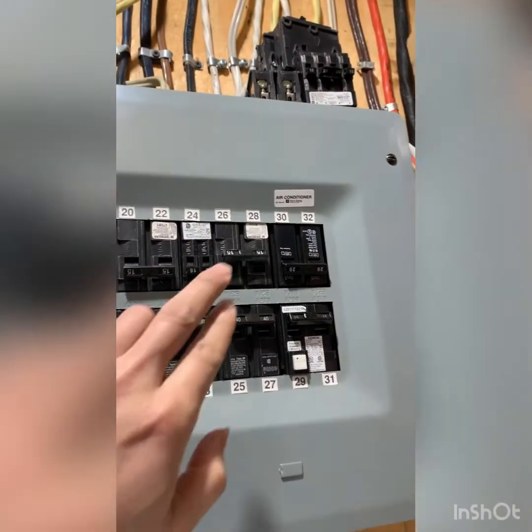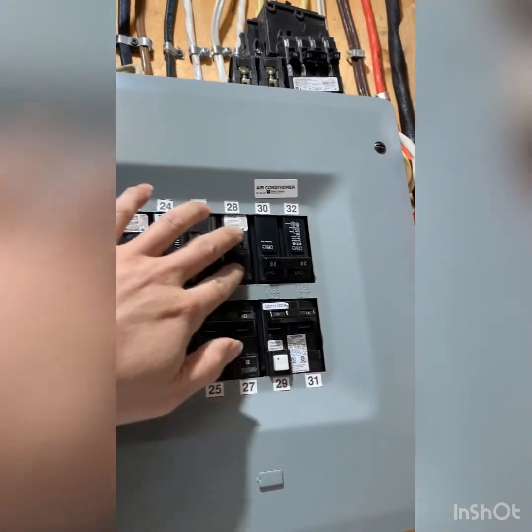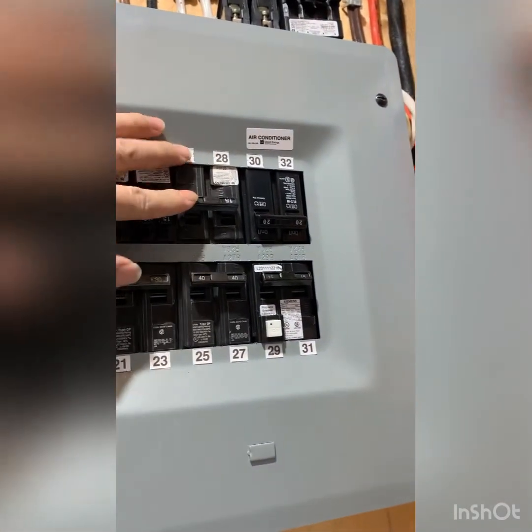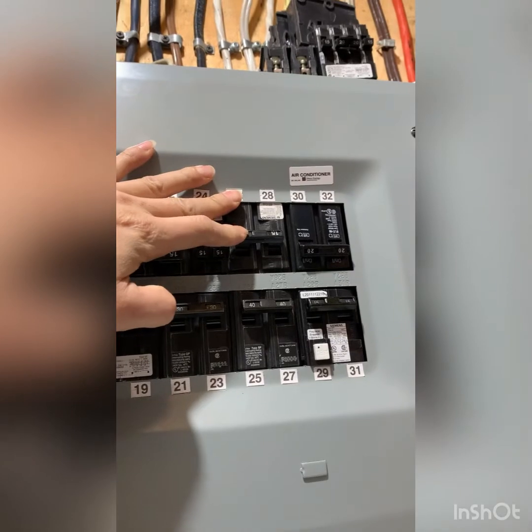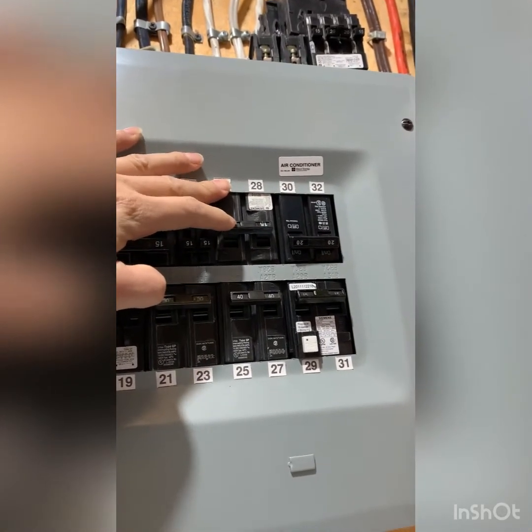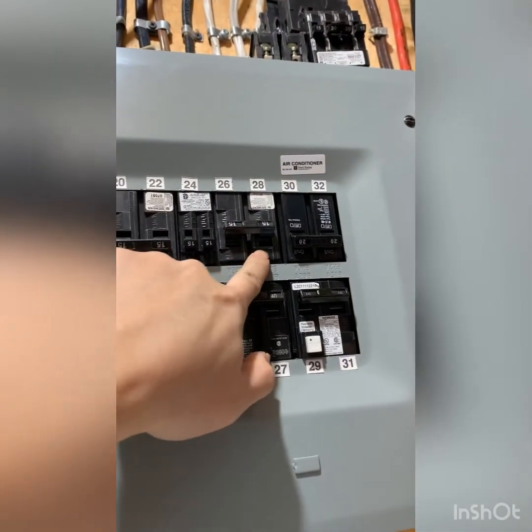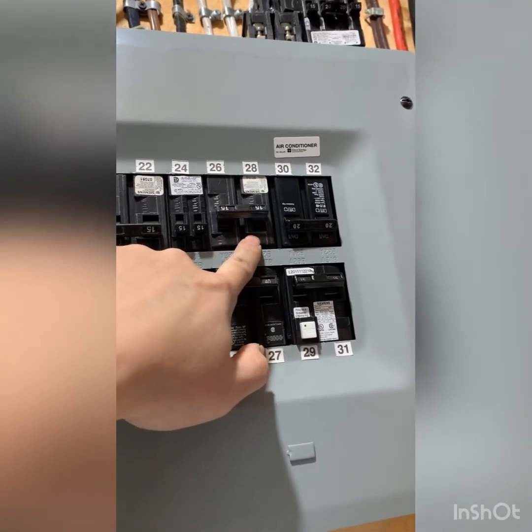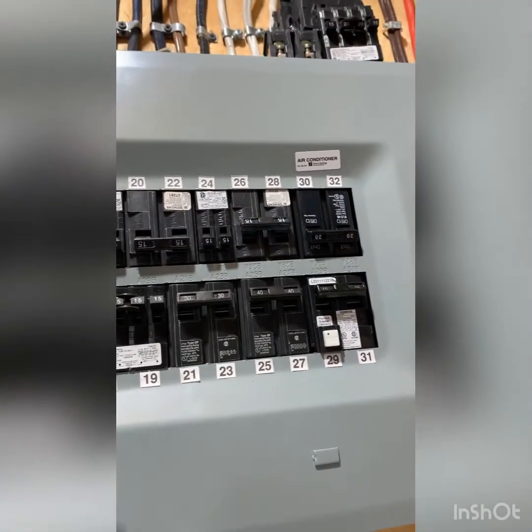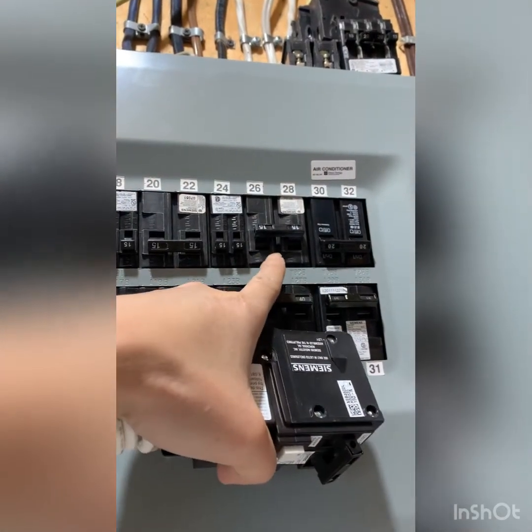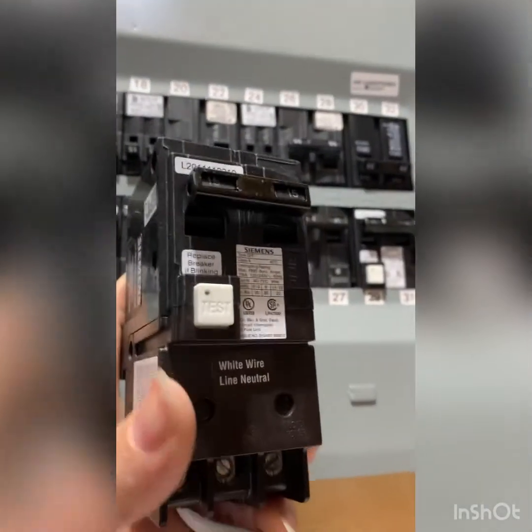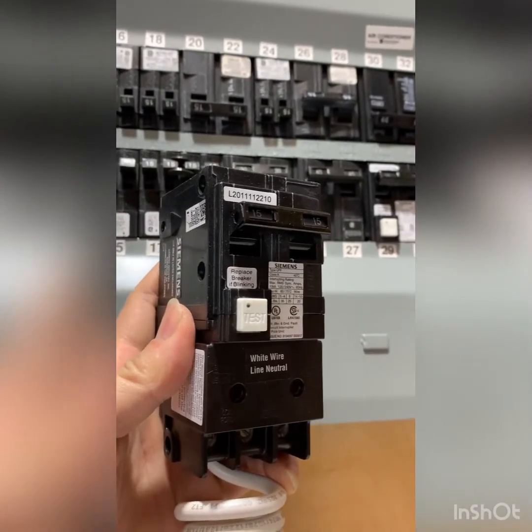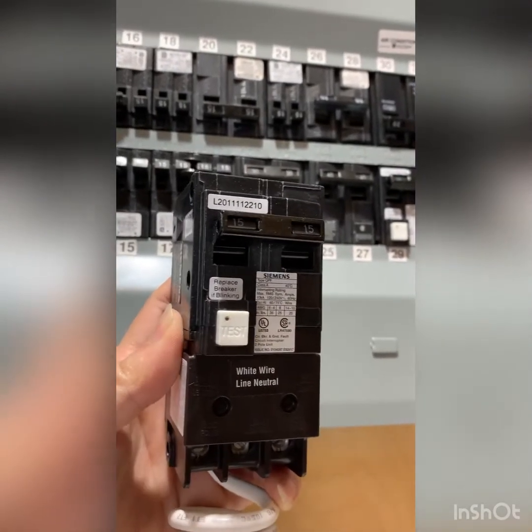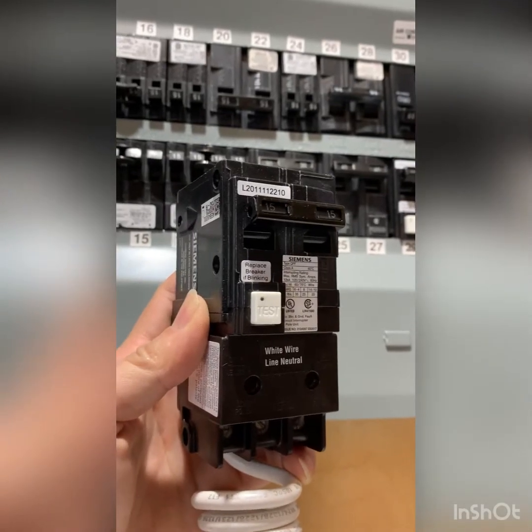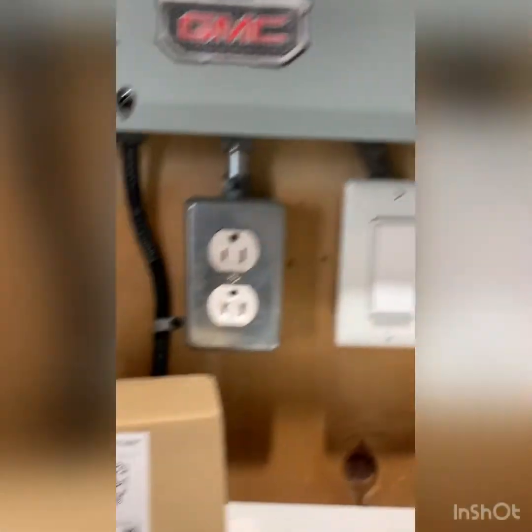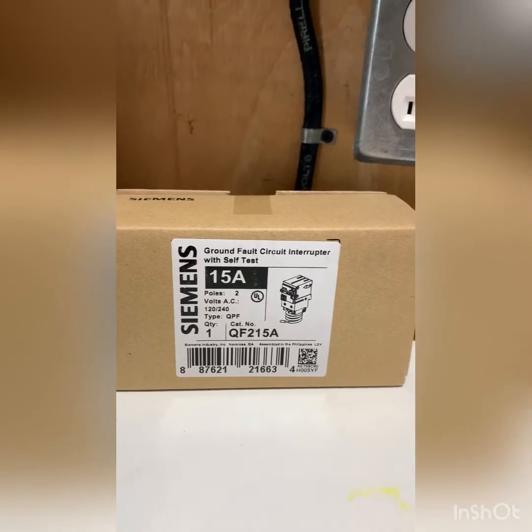Okay, here is the main electrical panel. These two breakers, this 2-pole breaker, is protecting the circuits for the split receptacle we just opened. Here, 26, 28. So I'm going to replace this old receptacle with the new one that has GFCI function, along with a 2-pole 15 amp circuit breaker. The product number is QF215A.